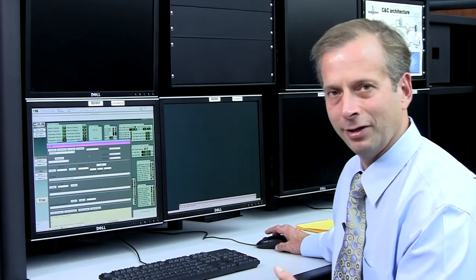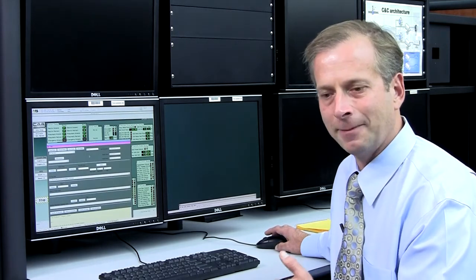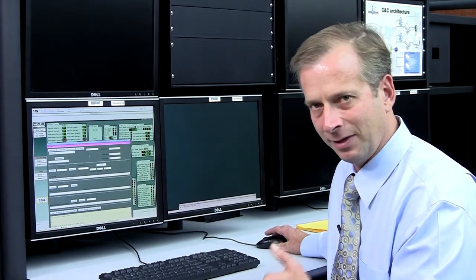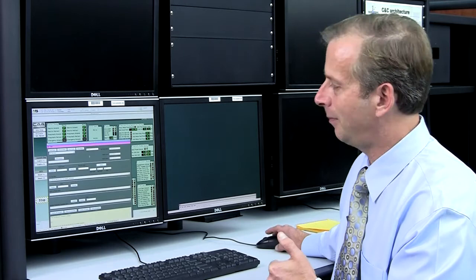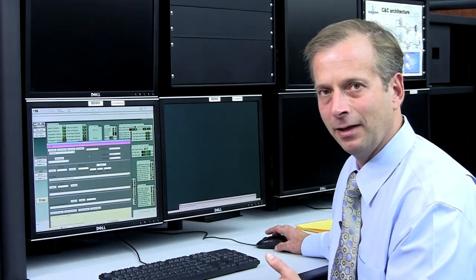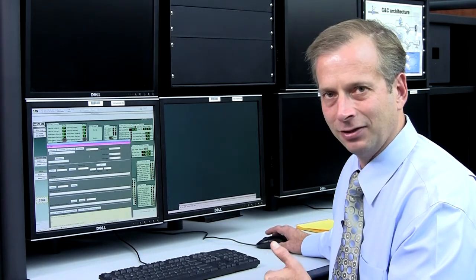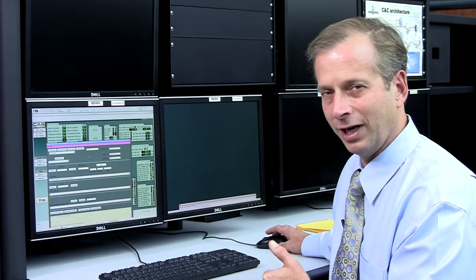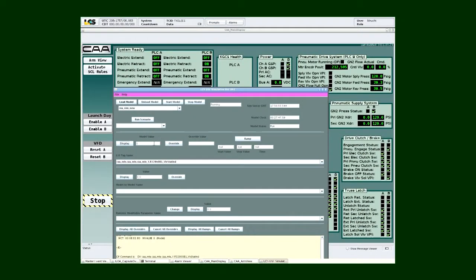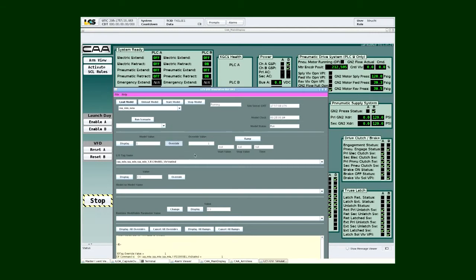What I'm going to do now is I'm going to override one of our limit switches. And the limit switch I'm going to override is the truss latch control valve limit switch. What I'm going to do now is I'm going to override this particular switch to a one. So I'm going to enter one. In my simulation interface, I'm going to select override. So what I've just done is I've sent a command to our simulation server, and I've told it to simulate that this sensor always reports in the on condition, regardless of what type of process our PLC is telling it to perform. So I've just basically simulated a shorted limit switch in the field.